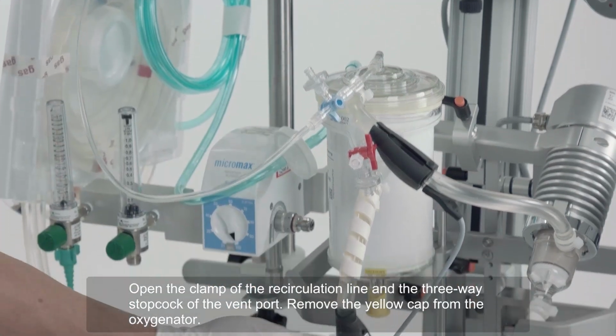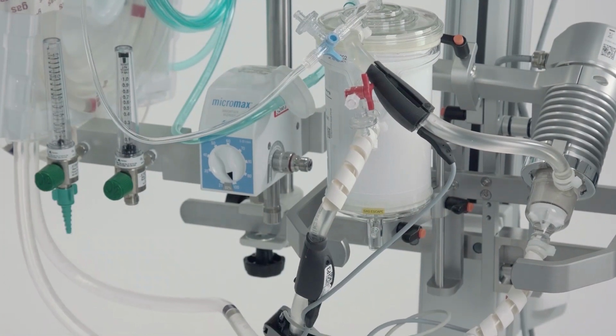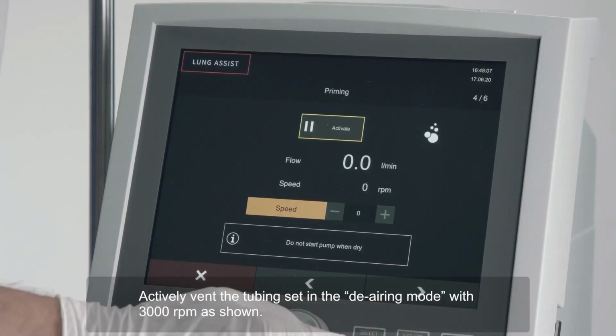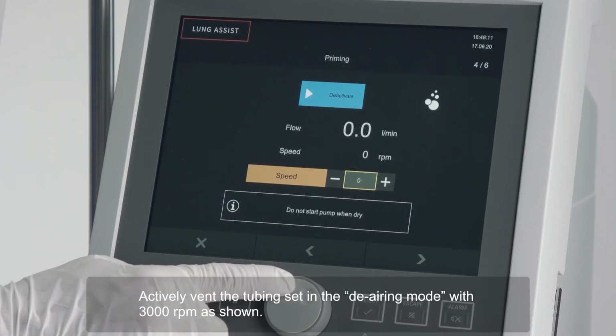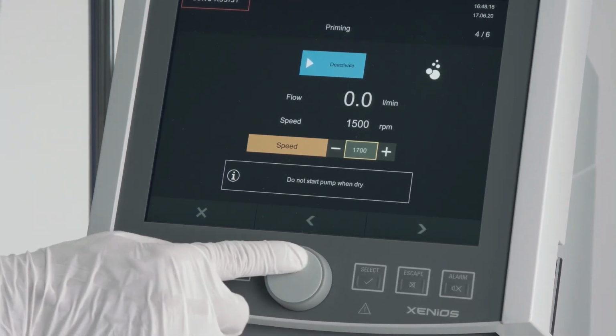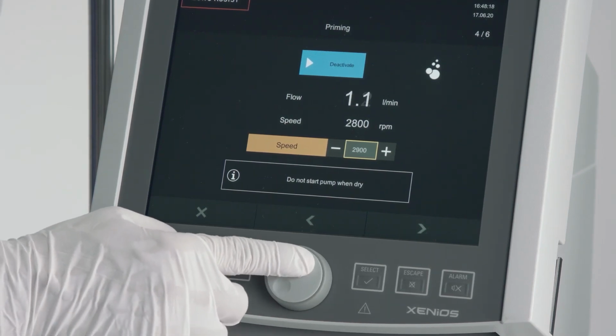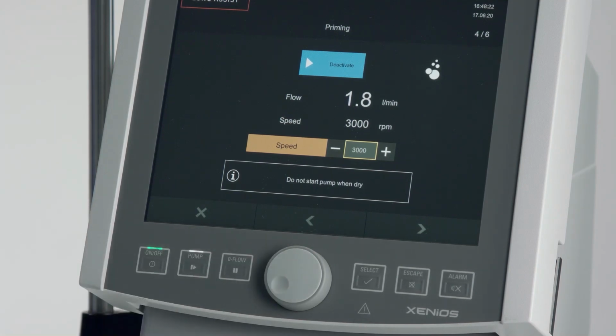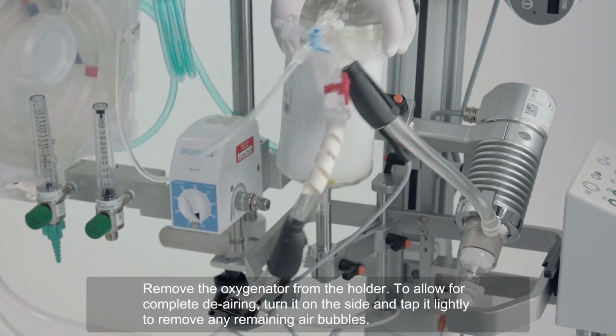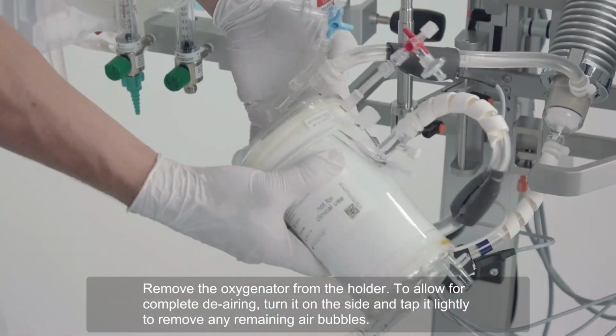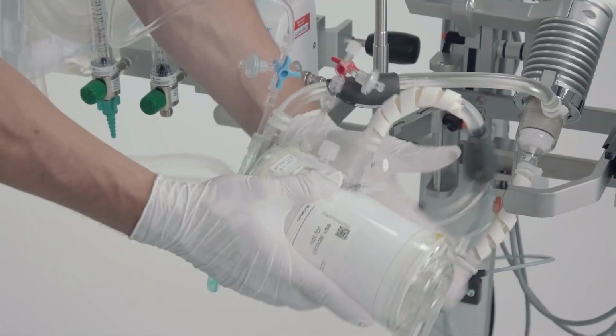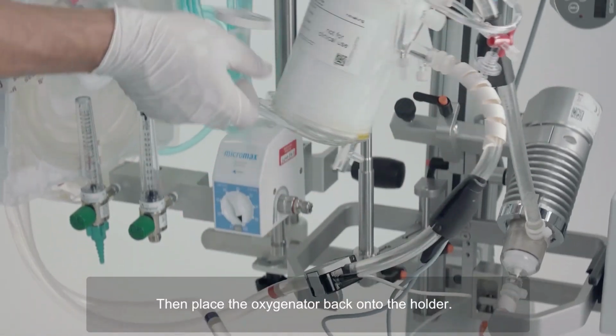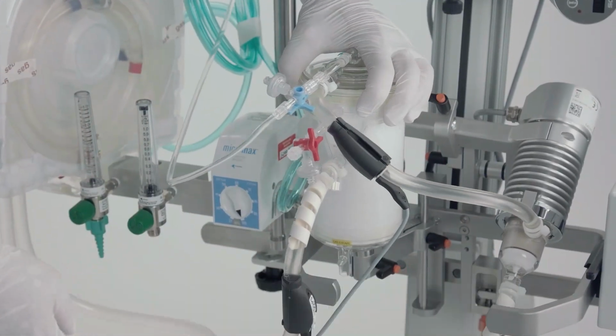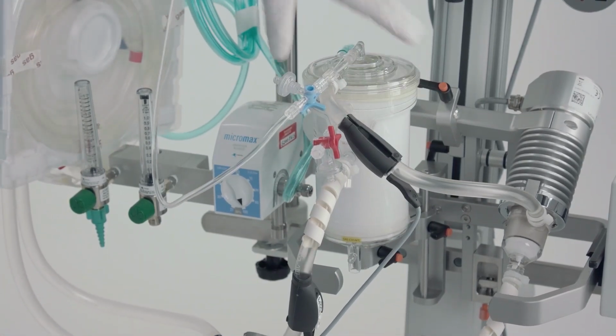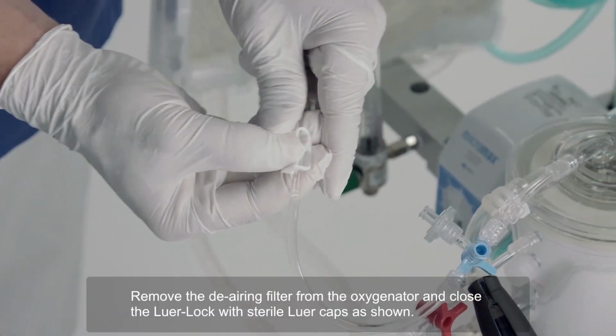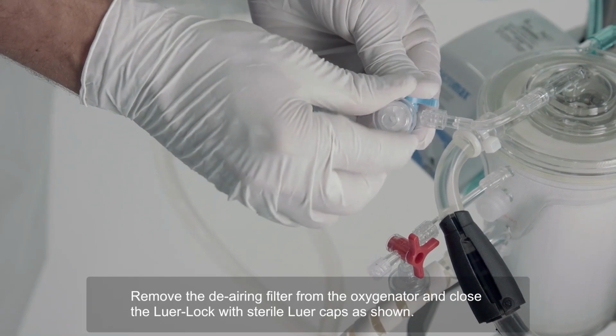Remove the yellow cap from the oxygenator. Actively vent the tubing set in the de-airing mode with 3000 RPM as shown. Remove the oxygenator from the holder. To allow for complete de-airing, turn it on the side and tap it lightly to remove any remaining air bubbles. Then place the oxygenator back onto the holder. Remove the de-airing filter from the oxygenator and close the luer lock with sterile luer caps as shown.